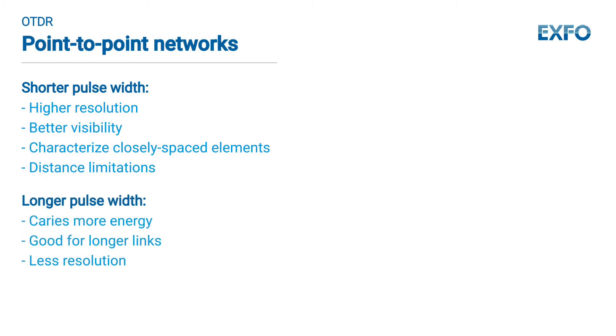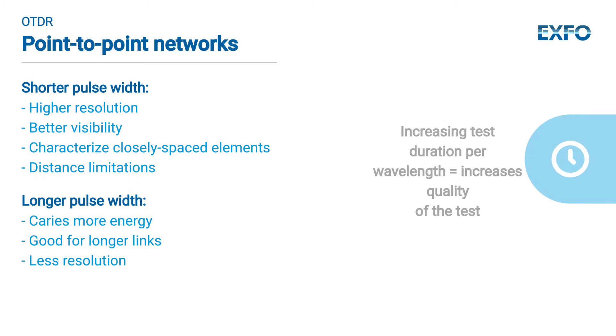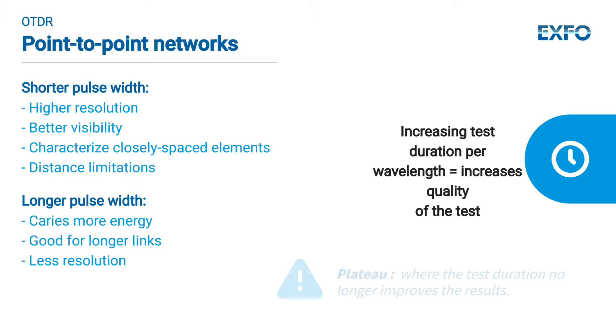A longer pulse width will carry more energy. This will test longer fiber links, but with less resolution, possibly masking some elements. It should be noted that the quality of the test improves when the data is averaged over a longer period, as it enhances the resolution for greater distances.